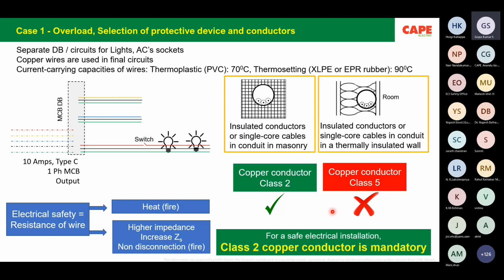Part 1, Section 17, Annexure B, has a table included: maximum allowed resistance of wires after pulling through a conduit. Because while pulling, there can be chances of damage to the wire. After pulling it through, we are supposed to measure the resistance of the wire and ensure that the continuity resistances are lesser than what is recommended in the table. In that table, the resistances considered are of class 2 conductor. So the simple statement is, if you use class 5 copper conductor in your building, you cannot claim that your building is in compliance with the National Electrical Code of India.